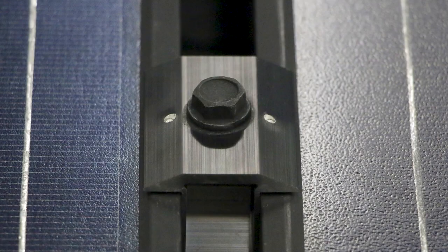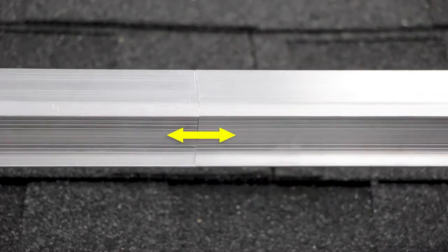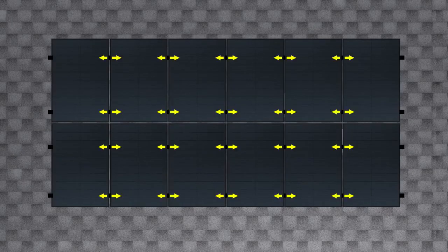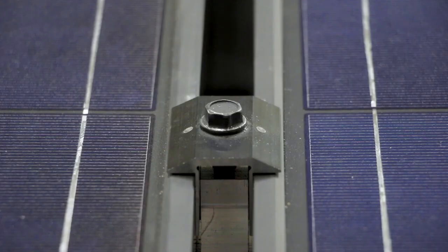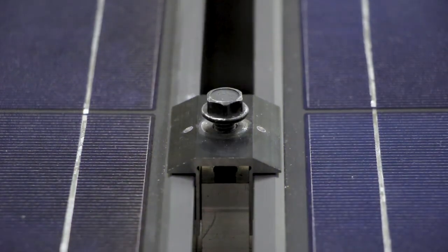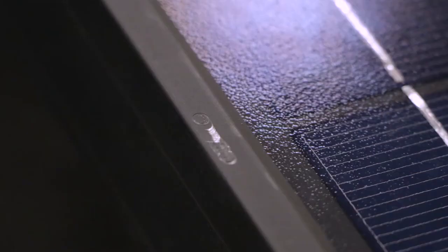The ClickFit system mid-clamps feature integrated bonding pins, so bonding and grounding the entire system is easy and straightforward. Rail segments are bonded together using the splice. Bonding paths in any given row are carried module to module through the mid-clamp. Mid-clamps are multiple use. However, if a mid-clamp has been removed after tightening, take care that the bonding pins bite into new metal to ensure proper bonding.